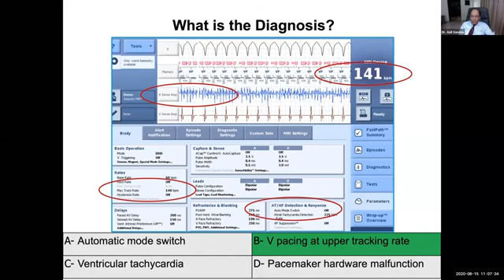So DDD, VDD and DDDR are all tracking modes. That is, the pacemaker will sense in the atrium and pace in the ventricle. The non-tracking mode is when the third letter shows only inhibited. Normally when the third letter is D, that means the pacemaker has a dual inhibited and triggered mode, so it is atrial inhibited and ventricular triggered. Whenever there is a sense, it will trigger a pace in the ventricle, but in the DDI or VVI, it will not do so.